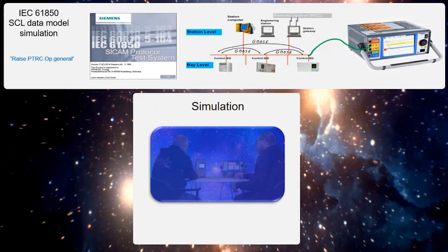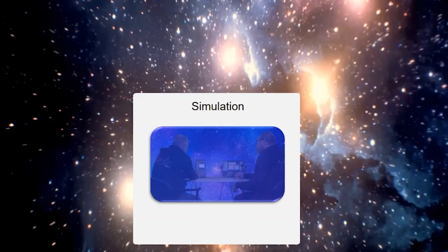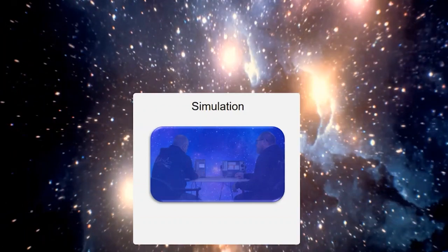into this data model, the general trip signal, and in the model that is written, when this signal goes up, send a GOOSE message. So the Siemens protocol test system will send a GOOSE message, or my test set will send a GOOSE message. But this GOOSE message related to the trip, for example, is not related to any injection of any power system fault. So it's not really this I want to talk about.